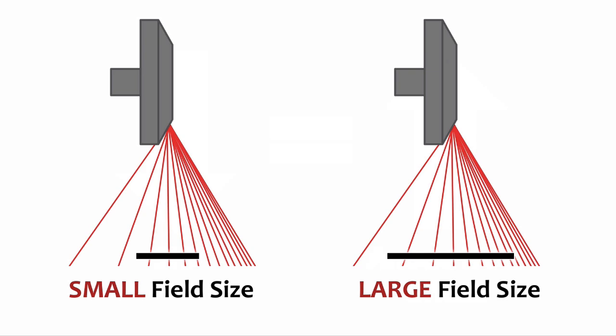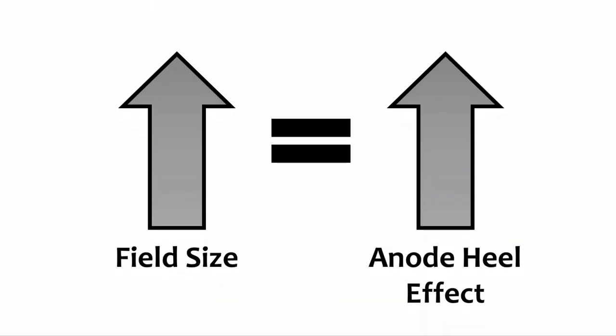The x-ray field size is one more factor that affects the severity of the anode heel effect. Increasing the field size increases the anode heel effect. Using a large field exposes the receptor to more of the low intensity beam on the anode side and more of the high intensity beam on the cathode side, resulting in an increased difference in intensity across the x-ray field. The relationship between field size and the heel effect is direct: as the field size increases, the anode heel effect also increases.